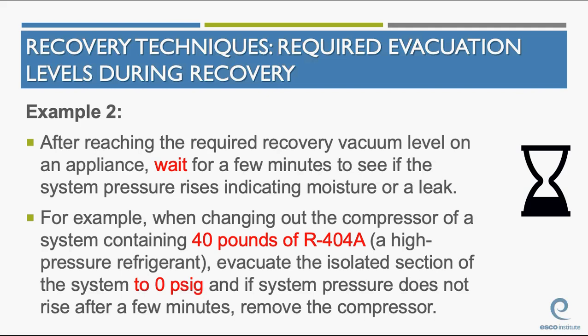Another example, when changing out a compressor of a system containing 40 pounds of R404A, which is a high-pressure refrigerant, evacuate the isolated section to 0 psi. If the system pressure doesn't rise after a few minutes, you can remove the compressor. Again, because it's under 200 pounds, we're now at 0 psi. Does everybody understand the change there? The difference is based on the weight of the amount of refrigerant that's in the system.